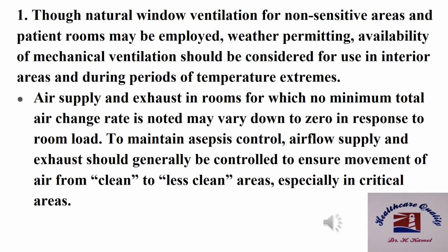Number one, though natural window ventilation for non-sensitive areas and patient rooms may be employed, weather permitting, availability of mechanical ventilation should be considered for use in interior areas and during periods of temperature extremes. Air supply and exhaust in rooms for which no minimum total air exchange rate is noted may vary down to zero in response to room load. To maintain asepsis control, airflow supply and exhaust should generally be controlled to ensure movement of air from clean to less clean areas, especially in critical areas.